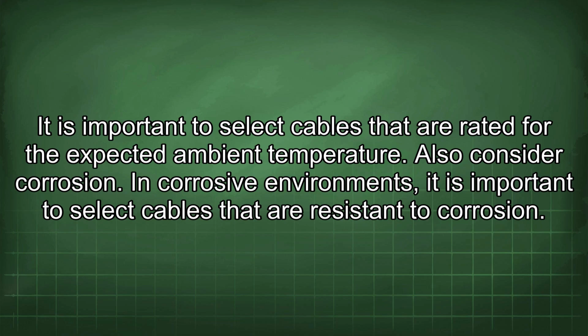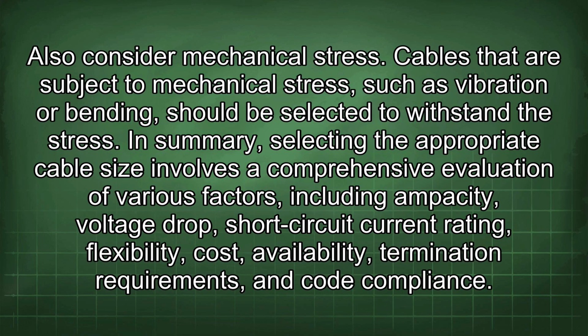Also consider corrosion. In corrosive environments, it is important to select cables that are resistant to corrosion. Also consider mechanical stress. Cables that are subject to mechanical stress such as vibration or bending should be selected to withstand the stress.